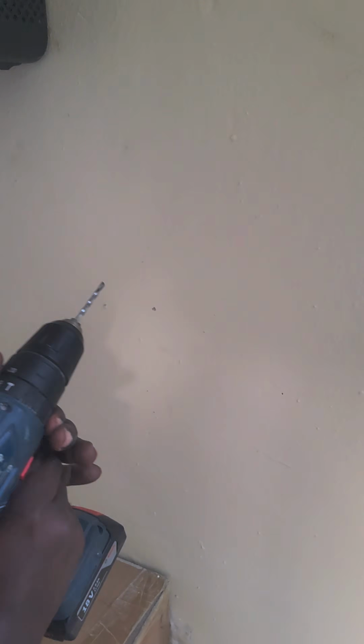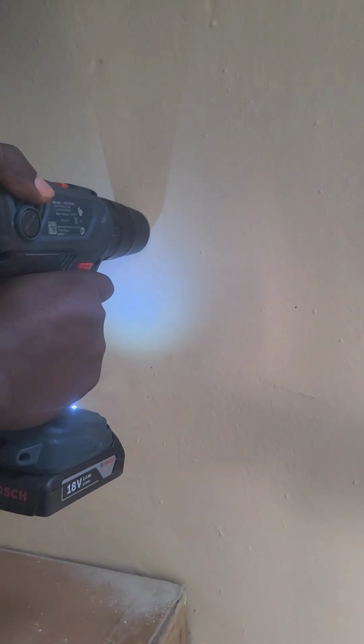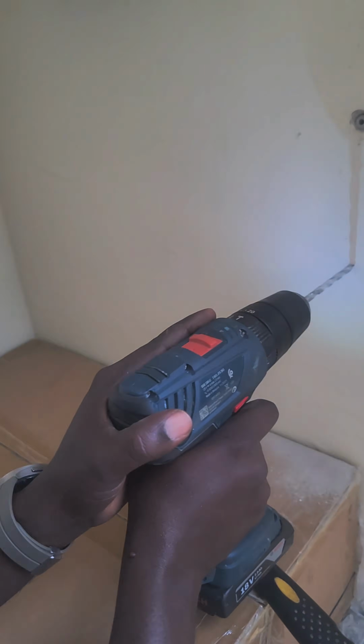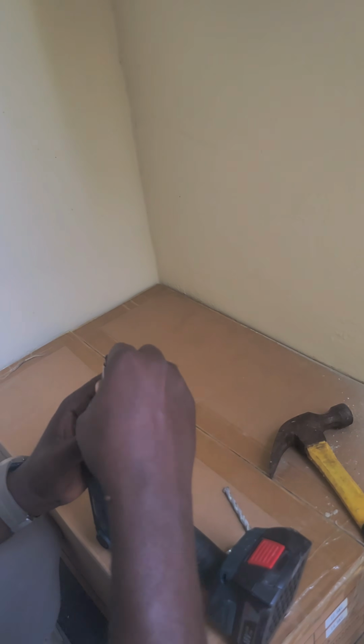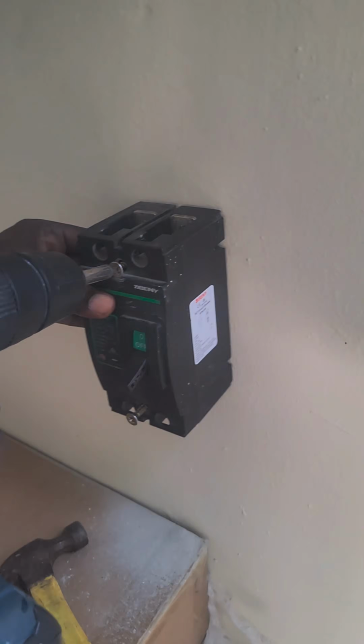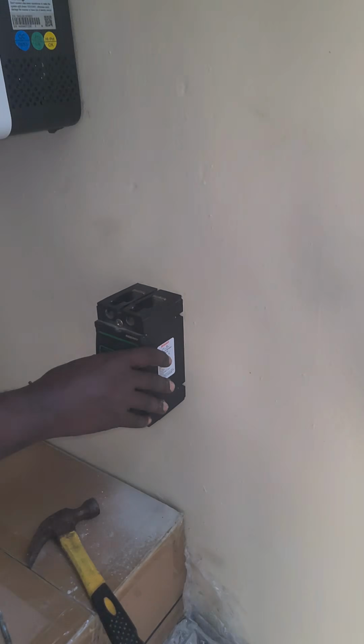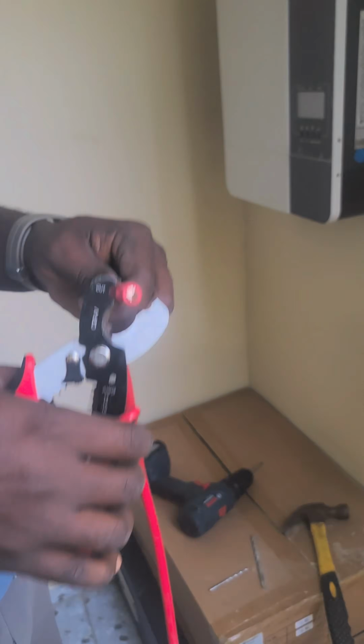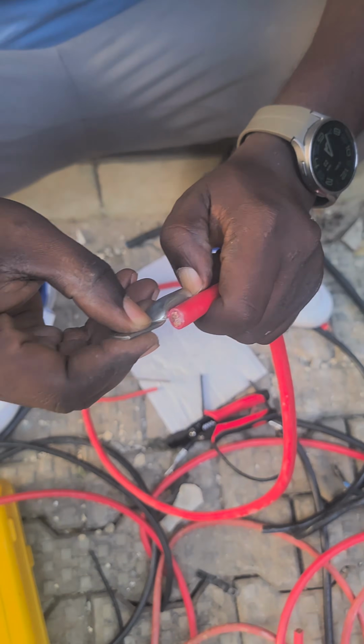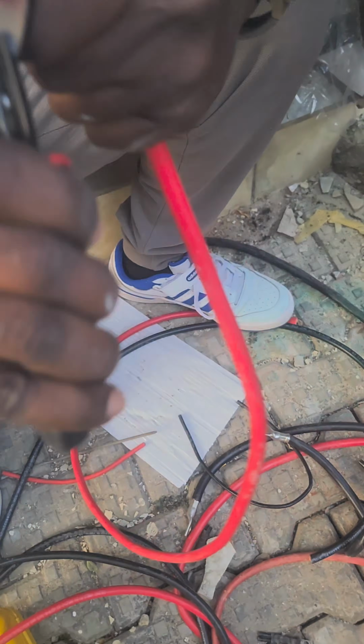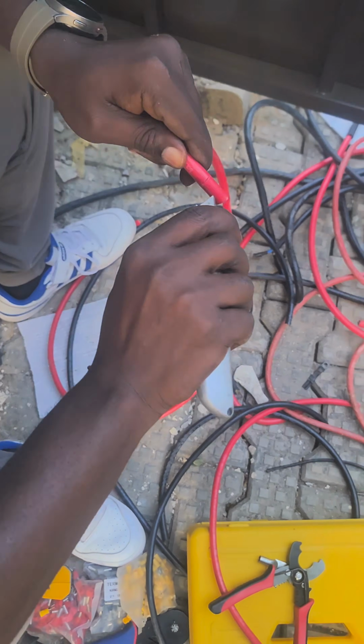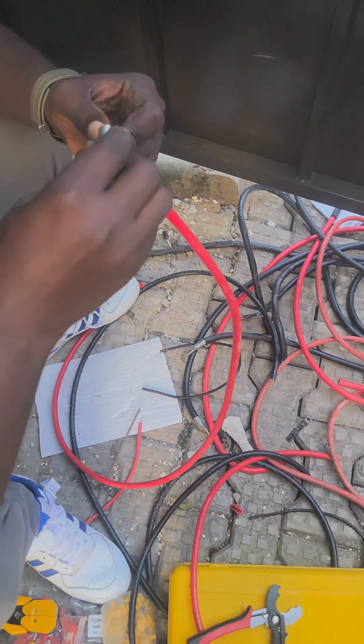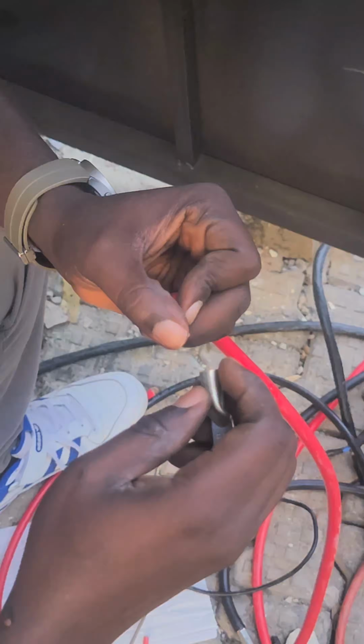And yeah, next I drill a hole. This is for the MCCB. The MCCB is a special kind of breaker that you use for high current applications, like between batteries and inverter. You can see how big and massive this thing is. So I installed it. The MCCB sits between the inverter and the battery. Again, it protects the inverter from the battery, and the battery from the inverter. So if there's a fault in the battery, it ensures that there is protection.